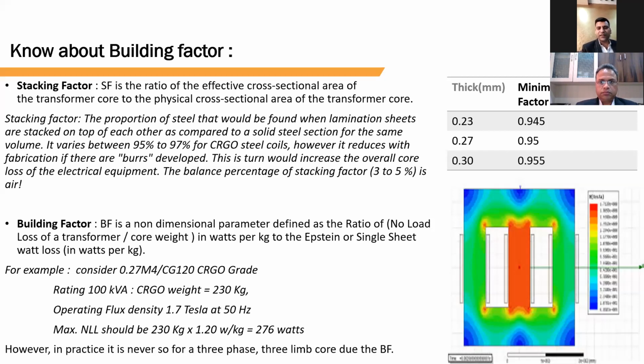Here on the right side of the table, I'm showing the minimum stacking factor requirement as per the IS standard, which from 0.23 mm thickness is 0.945, and maximum in 0.3 it should be 0.955. So this is the minimum stacking factor requirement. Basically, if your stacking factor improves, then your no load loss will also improve, because there will be less air gap and less burr. So hope with this explanation we understand that stacking factor is related to the stack height of the limb. The cause of stacking factor is air gap and burr.